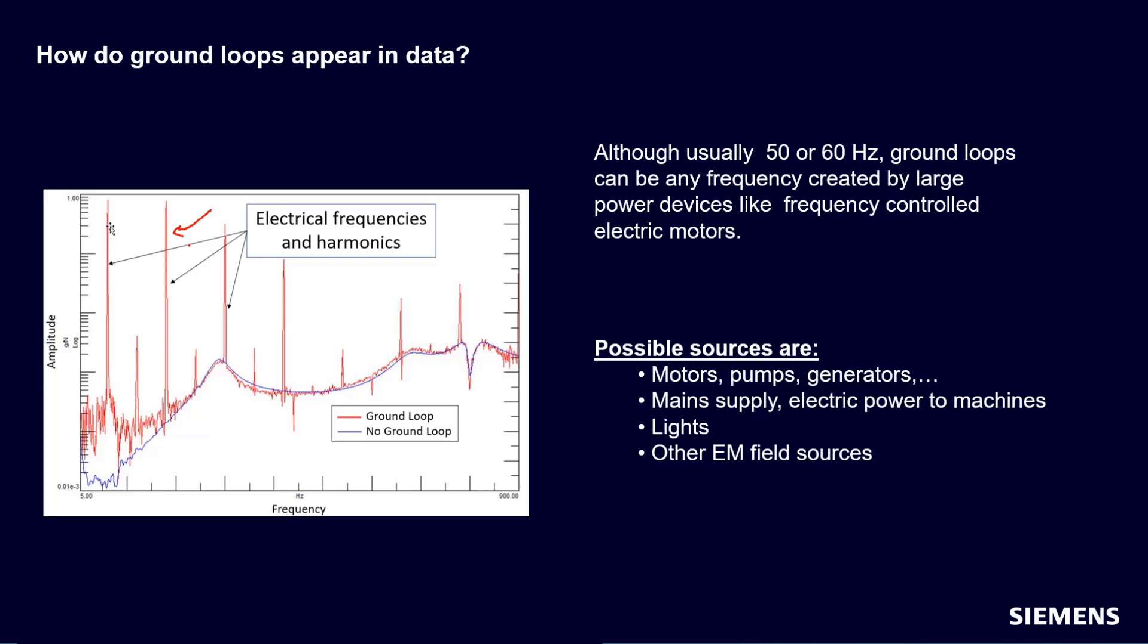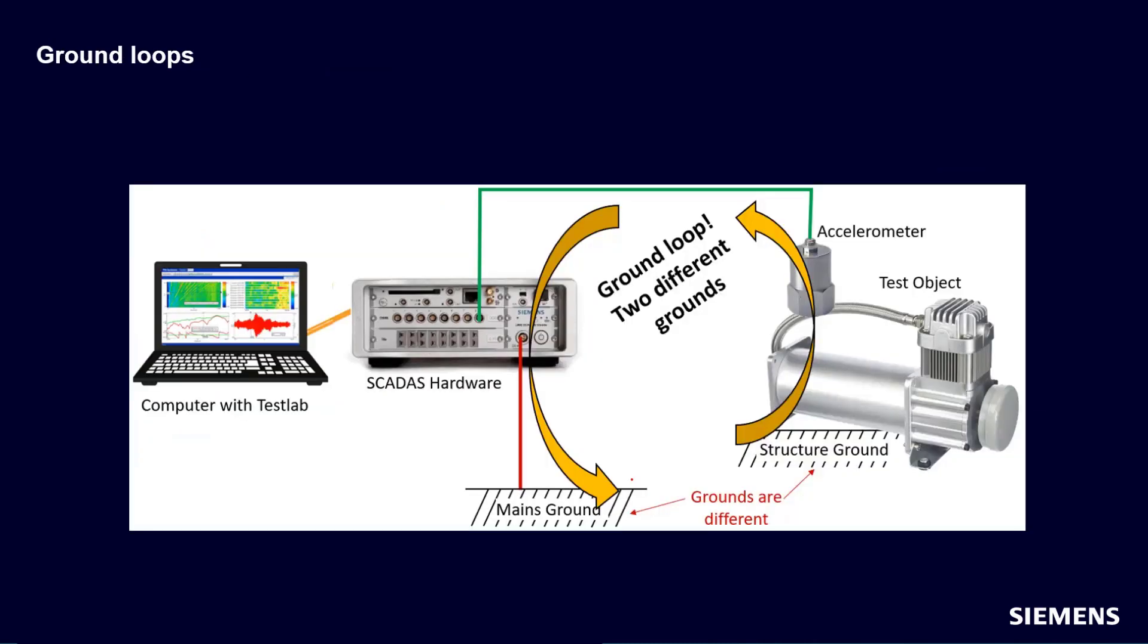Probably not a good idea to stake your whole career on, like hey, there's some bad vibration at 60 hertz, right, because that may not be coming from the vibration of the test object, but might be coming from a nearby power generator, the lights in your lab, or something like that. Yeah, I'd be very suspicious of any 60 hertz problem. Very lightly damped 60 hertz problem. So if someone's talking about a lightly damped 60 hertz problem, you might want to do some double checking.